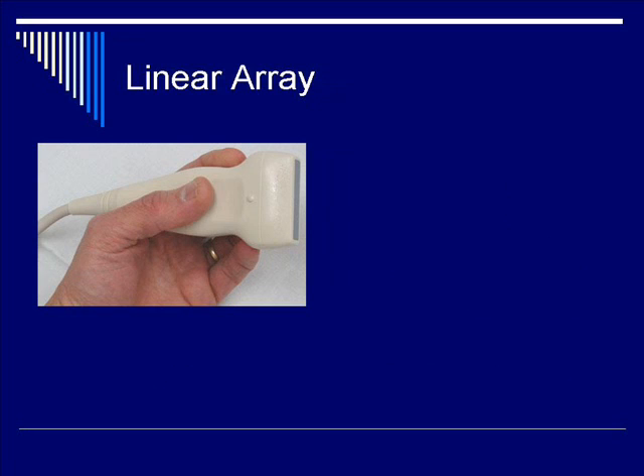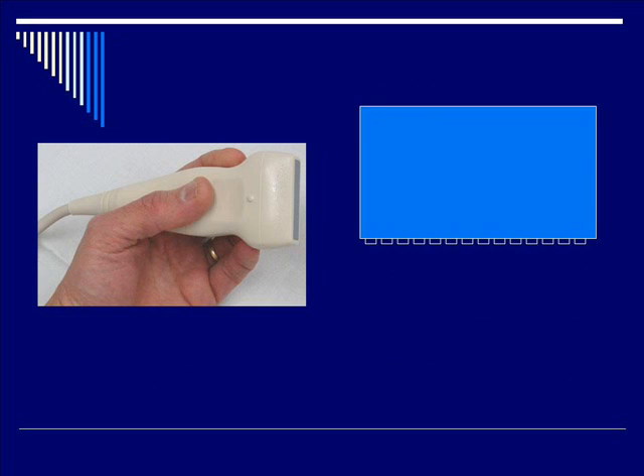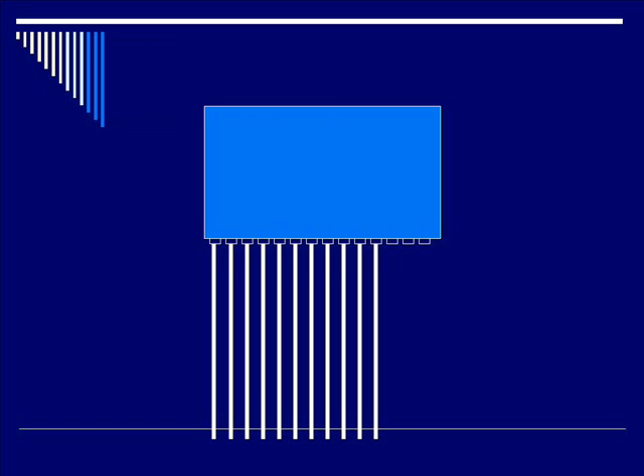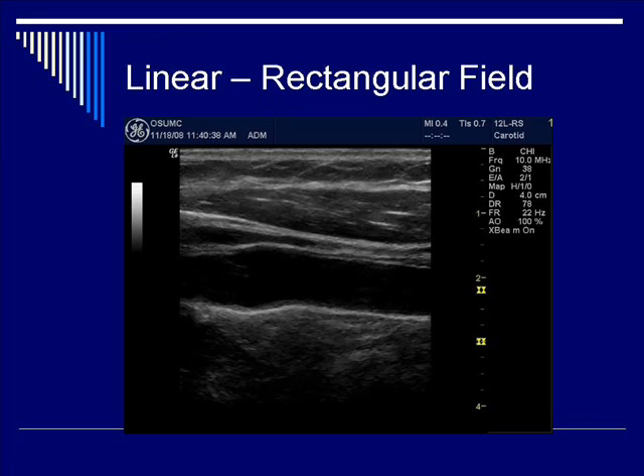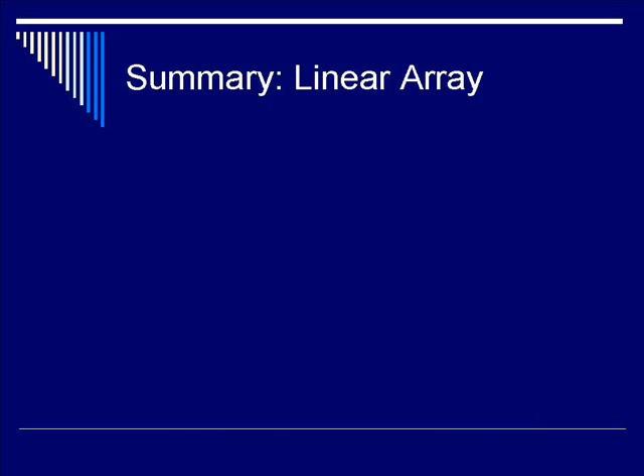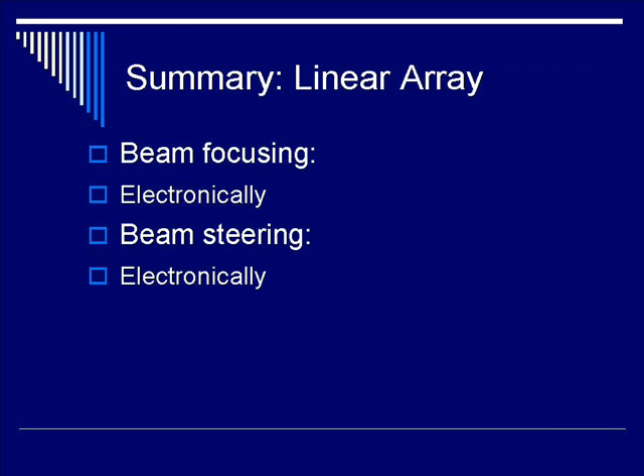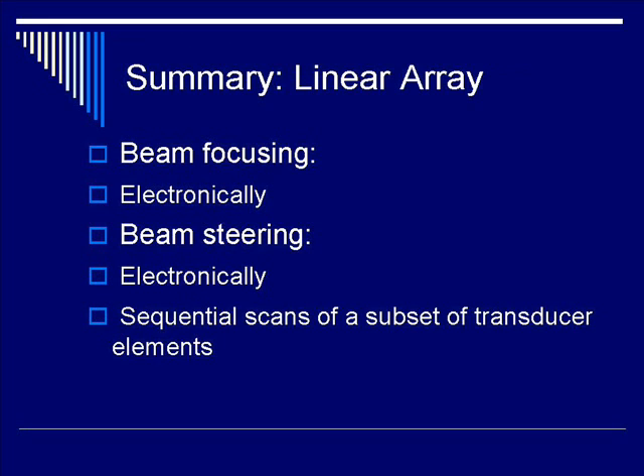This picture is a typical linear array. The cartoon rendition shows a rectangular profile with multiple piezoelectric elements at the surface. You scan each element or group of elements from left to right sequentially to produce a rectangular scan pattern of the soft tissue of interest. This is an example of some surface blood vessels scanned using the linear array. In summary, a linear array has a beam that is focused and steered electronically, done via sequential scans of a subset of transducer elements.